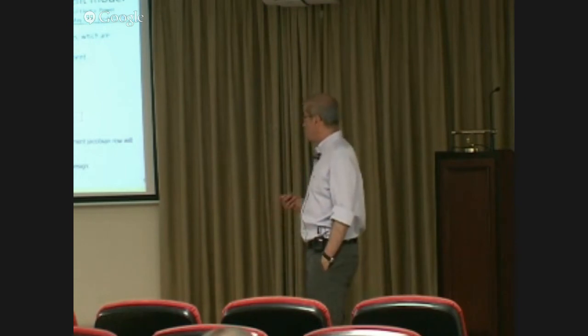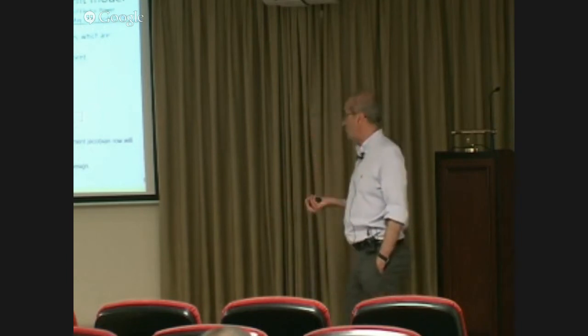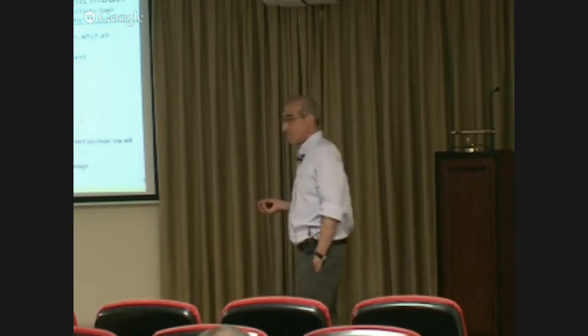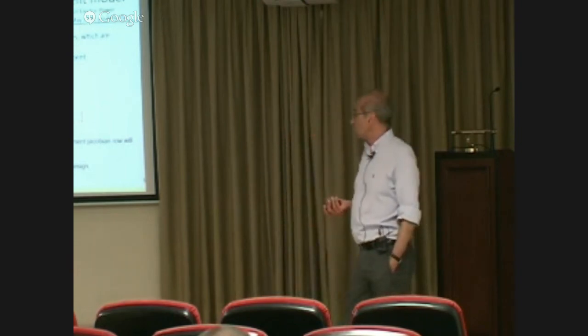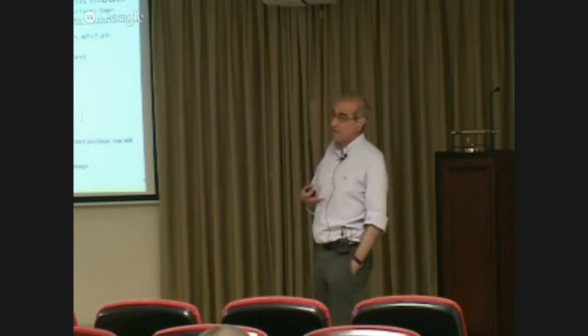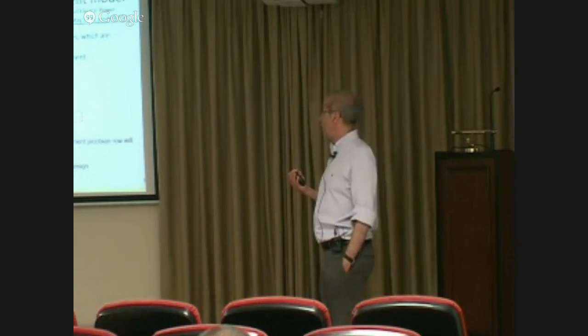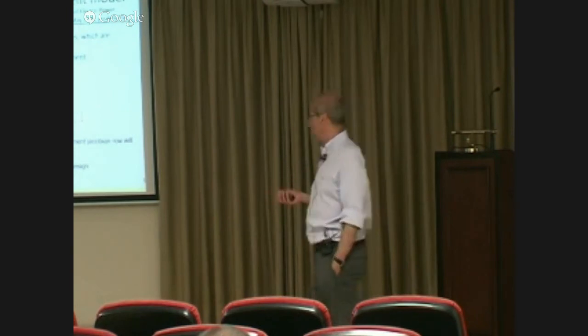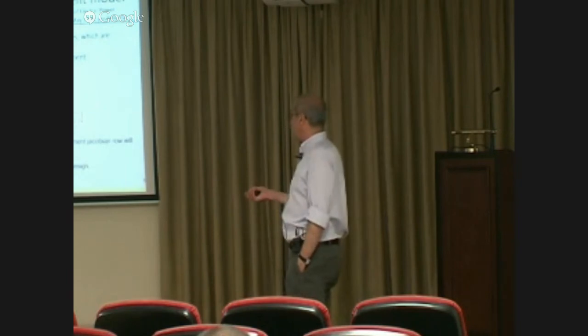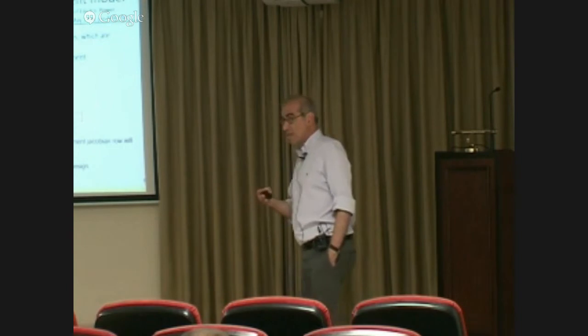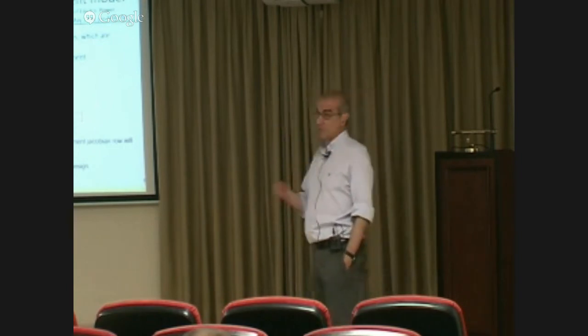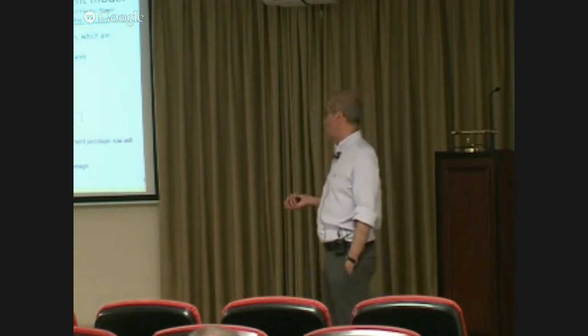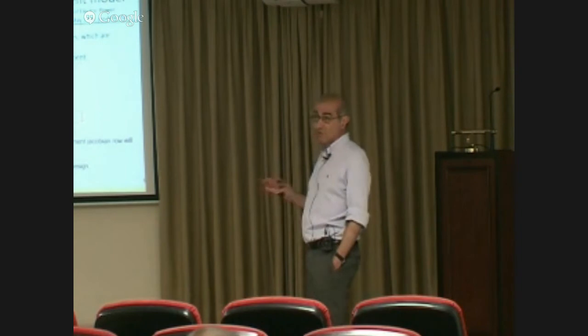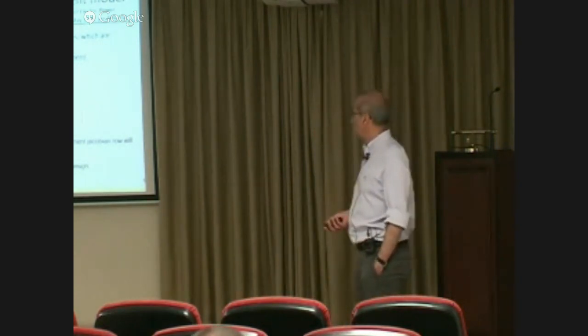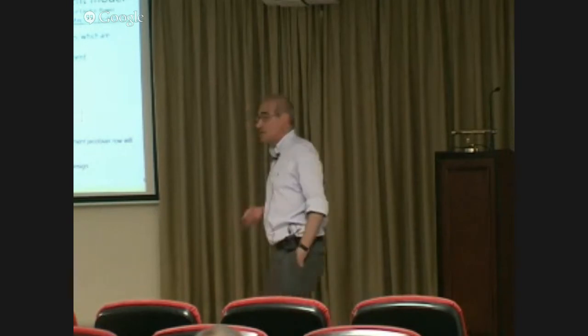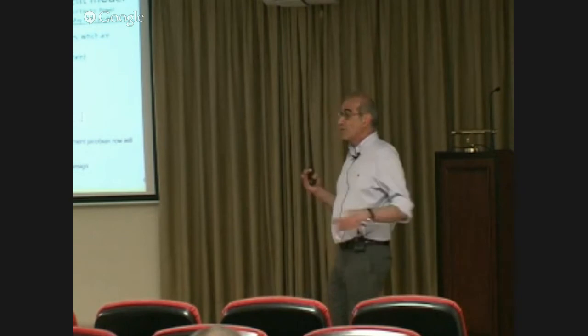So scaling is a trivial way to get rid of leverage current measurements. Once you do that, you can guarantee there will be no leverage measurements in your set. So this is an advantage over using SCADA measurements when applying L1 to state estimation. Furthermore, if you have zero injections and want to use them, it's very easy, because L1 uses linear programming, and equality constraints are almost implicitly taken care of in linear programming. So you can easily do those things without changing the weights. There's no need to play with the weights, and that's not going to cause any leverage. So this is an advantage, and we can revisit L1 to see what happens now that we have these advantages when using phasor measurements.